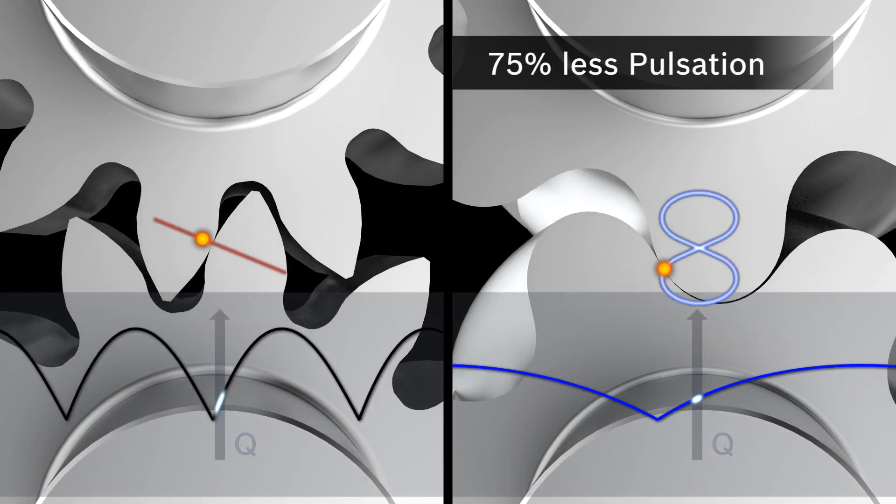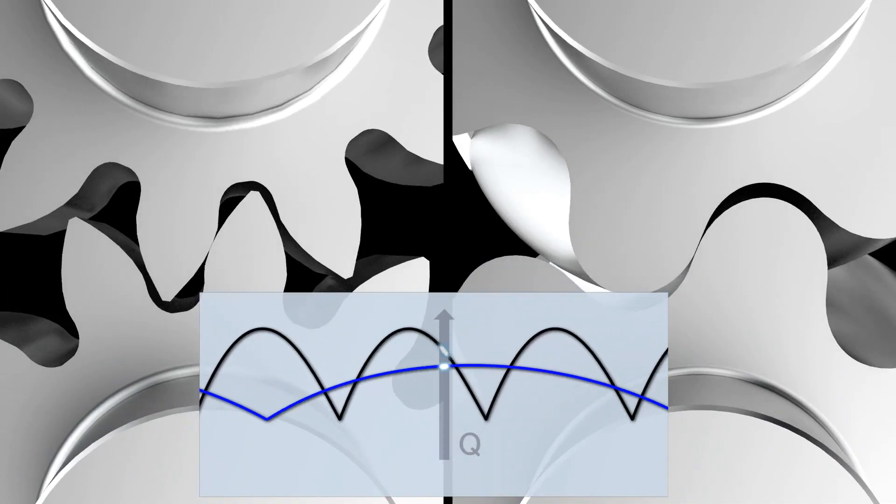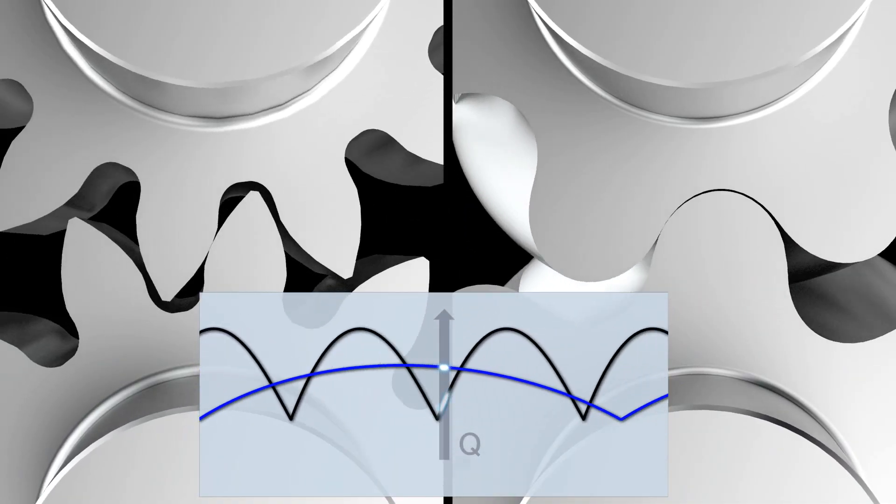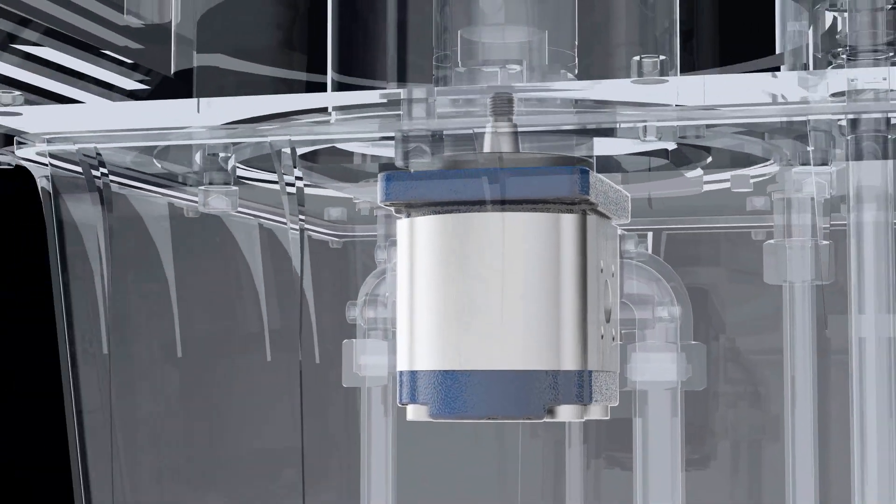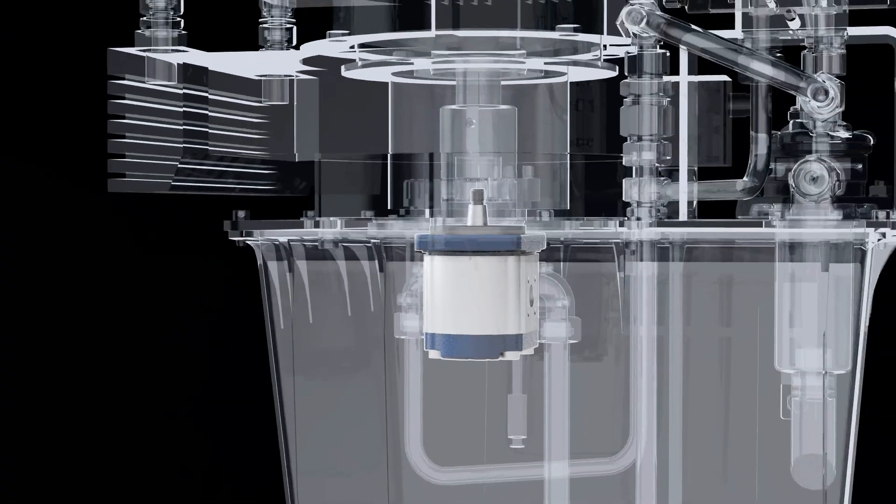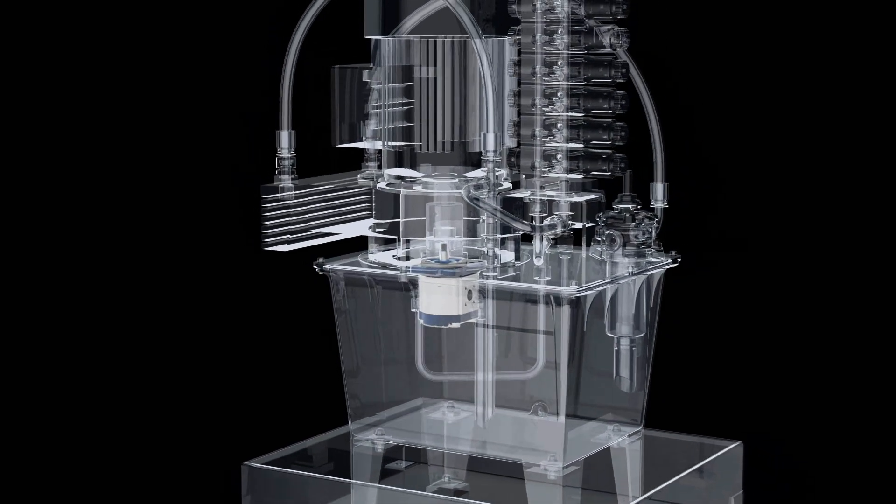Flow pulsation reduced by 75% minimizes vibration in the machine and a 35% lower frequency results in a more pleasant sound. The very low pulsation reduces the vibration tendency of other components in the hydraulic system. This is how Silence Plus ensures greater quiet in the entire machine.